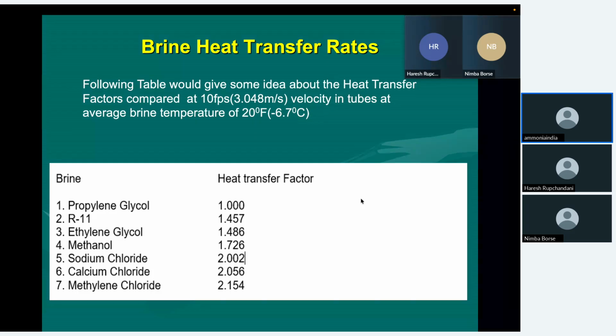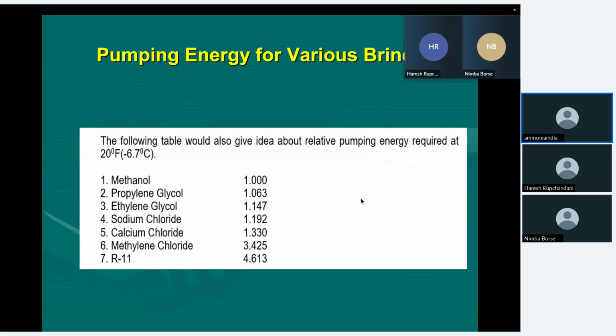Now I will tell you another interesting example of the use of propylene glycol. In one of the Bombay plants, they were using propylene glycol for shell and tube chillers, and it was a German design plant. At 8 o'clock in the evening, I got a call that your plant design is totally wrong and constantly liquid is coming to the compressor. So come down immediately. All of us are waiting even at night time. So I rushed to Bombay.